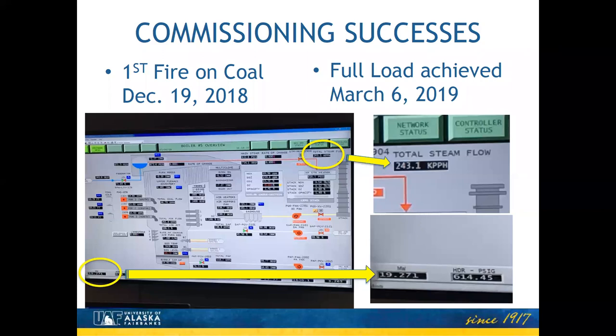The boiler's rated to produce 240,000 pounds of steam per hour. And so the number up on the top right there shows the total steam flow coming out of the boiler, and we were able to get it to that 240 kpph level. And then down in the lower left corner of the screen, that shows the amount of electricity that the steam turbine generator is producing. It's rated to produce 19 megawatts, and we were able to get it there. So when the plant runs, it runs very well. We're quite happy about that.